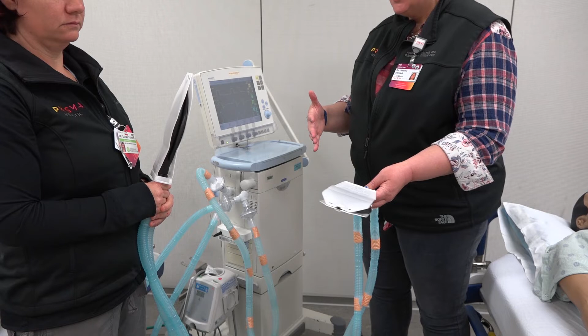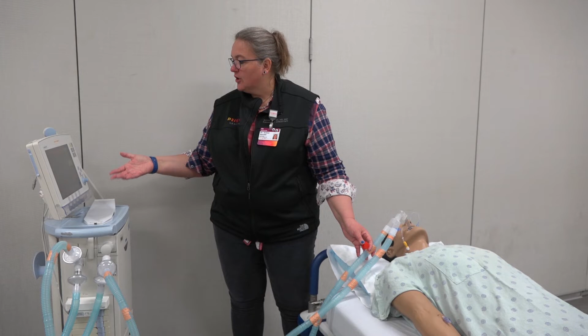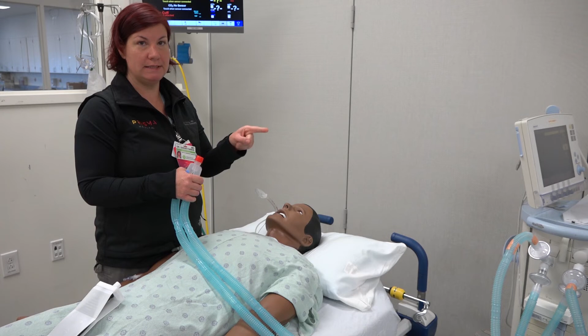So now I'm going to pause our ventilator, and we're ready to attach it to our patients. So now we're going to connect patient A and then patient B. So patient A is connected. My alarms are actually set for 2 patients, so our alarms are going to go off because we have half of the tidal volume that we initially set on the ventilator. So you want to make sure that the tidal volume is appropriate, and then you can connect patient B. And now I'm going to attach patient B to the ventilator, and we'll save the cap and have it labeled and taped to the ventilator in case we need to take a patient off emergently.